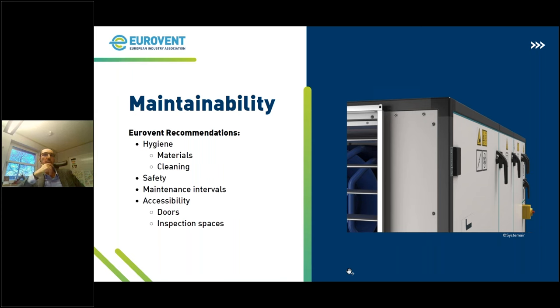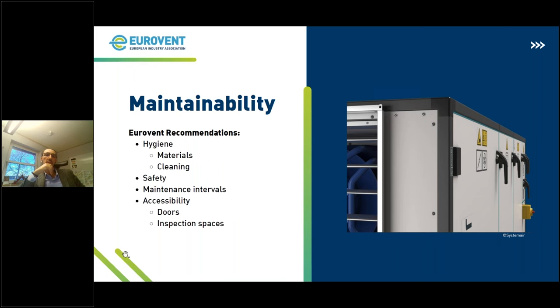When it comes to maintenance intervals, not all functions require the same frequency of maintenance. For example, if we think about a unit with humidification, the humidification process makes the inside of the unit humid, which can create issues if not maintained in time. The interval of maximum maintenance should be maximum six months. If the unit doesn't have humidification, it should be maintained in an interval of maximum 12 months. Depending on whether the unit has humidification or not, the in-depth hygienic review of the unit should be done every two or three years, respectively.